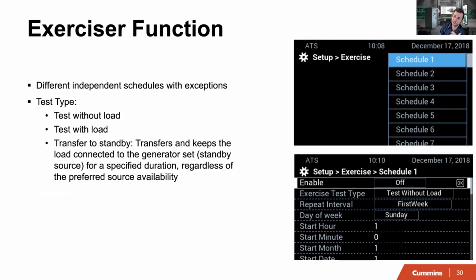And obviously we need to hopefully do exercising on the generator set and transfer switch. It's also required by code. So there are multiple ways to do this, multiple programs that you can program with exceptions, and you can do test with load, test without load, or do a storm avoidance if we want to stay connected to the generator. For example, if there's a storm rolling by and the utility is available, but we want to stay connected.